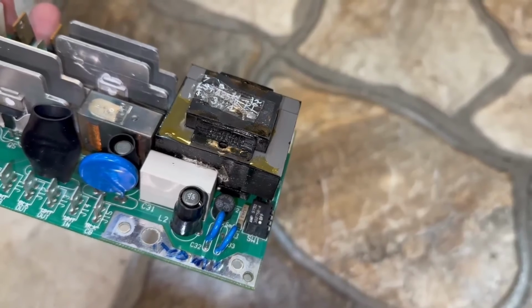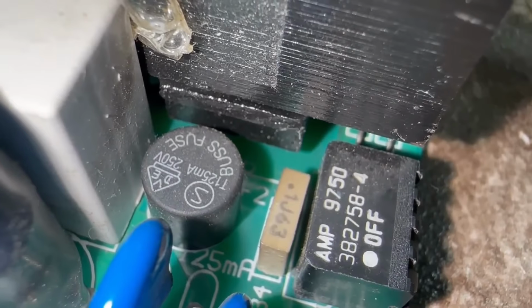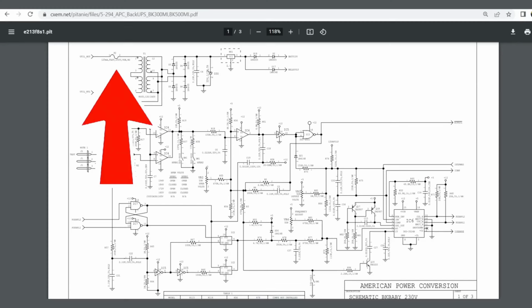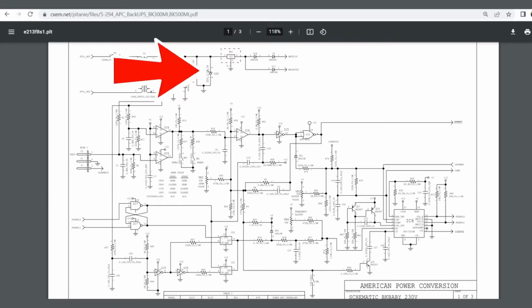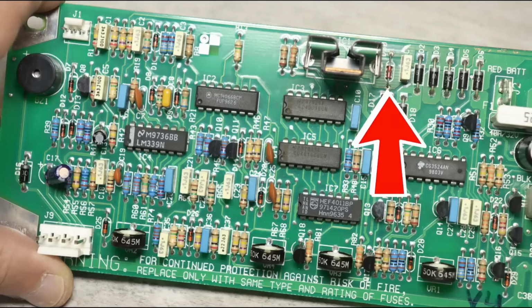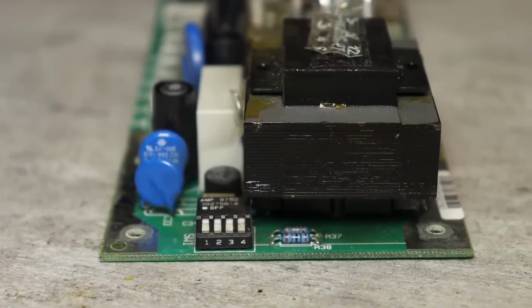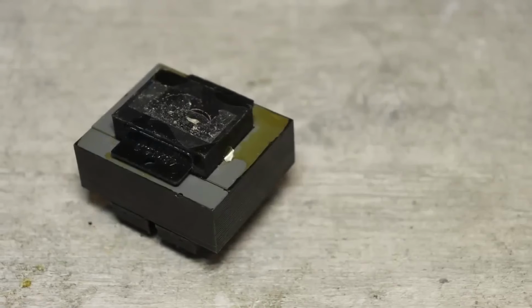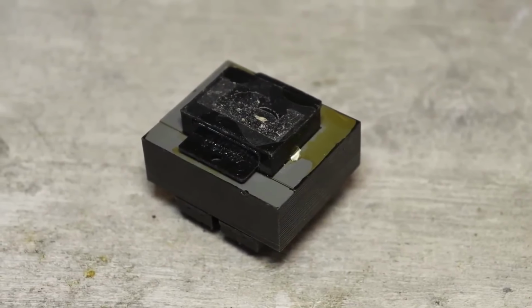It turned out there was a blown fuse in the primary circuit. I put in a jumper, connected it, and a Zener diode that was shorted started to heat up. After removing it and turning the unit on again, the transformer heated up to 100 degrees in 10 seconds, and as it turned out later, it was burnt out.